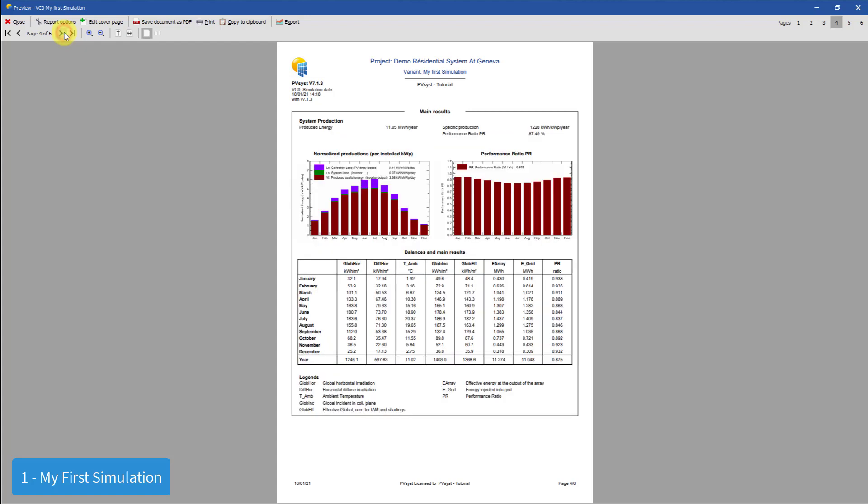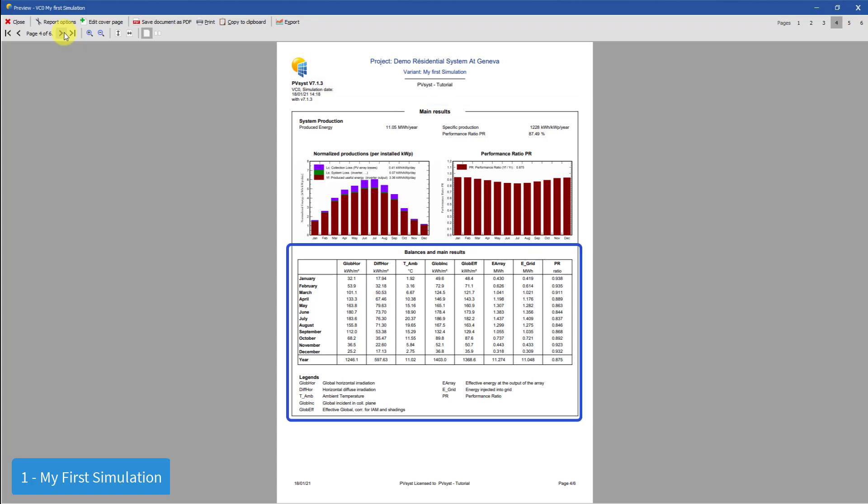The fourth page shows the main results. The graphs at the top show you the normalized production of the system and the performance ratio over the year. The normalized production shows collection and system losses as well as the useful energy produced per kilowatt peak of the installed PV modules. This is paired with a graph of the performance ratio for each month of the simulation. A table showing the balances and main results for each month as well as the whole year is also given.